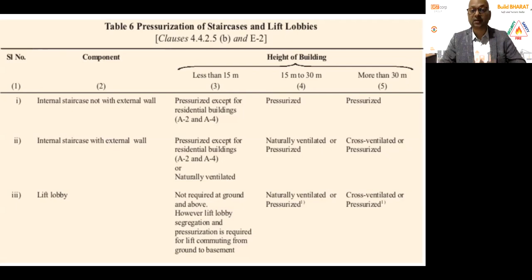This is for pressurization of staircases, where to do it and where not to. When natural ventilation is mentioned, NBC gives a specific guideline of 0.5 square meter opening, which can be cross ventilated in the same area or on an external wall. That's the minimum given. But there may be areas with very large staircases, where you'd need more than 0.5 square meters. And if you don't get a cross ventilated or naturally ventilated lobby, you need to construct more than 0.5 square meter area on the same wall.